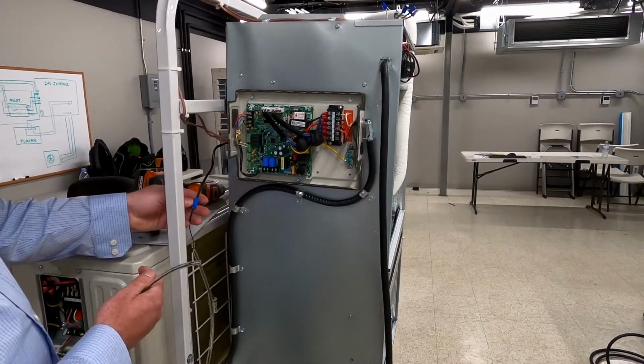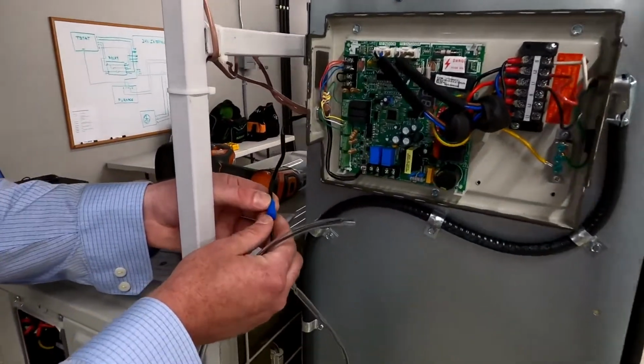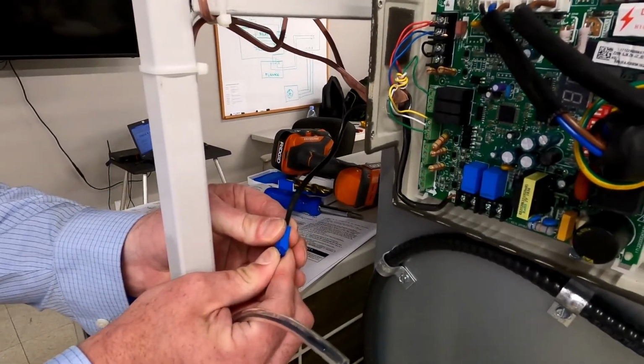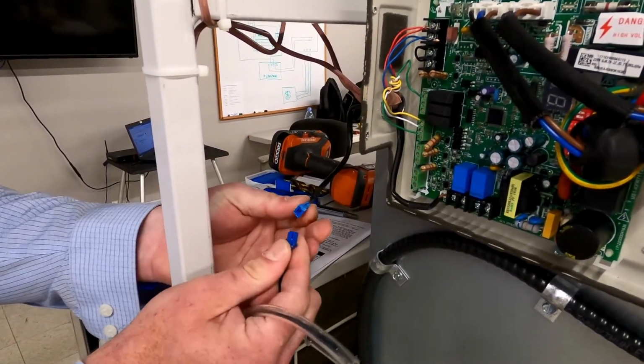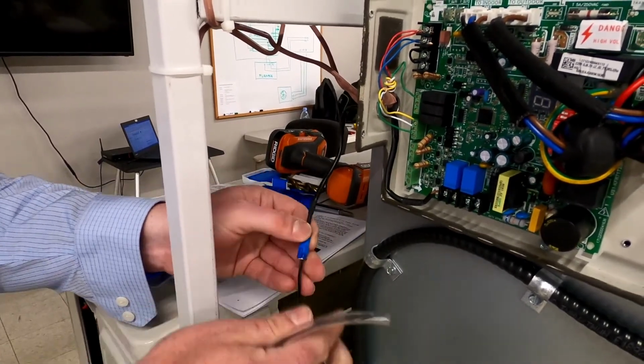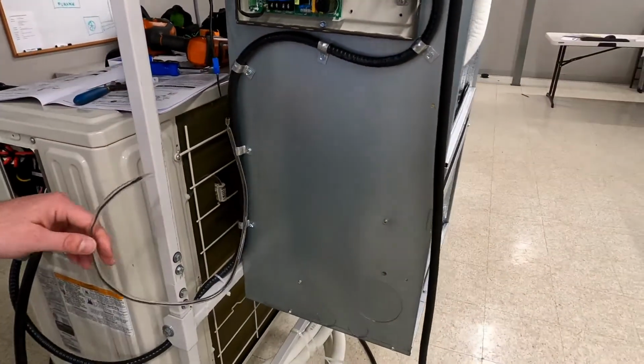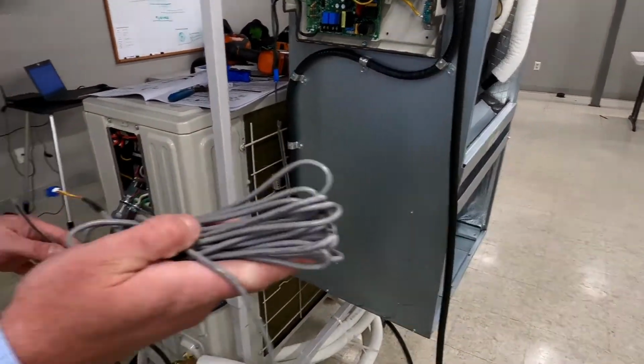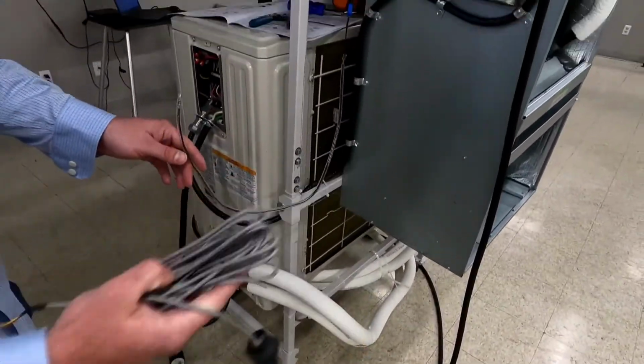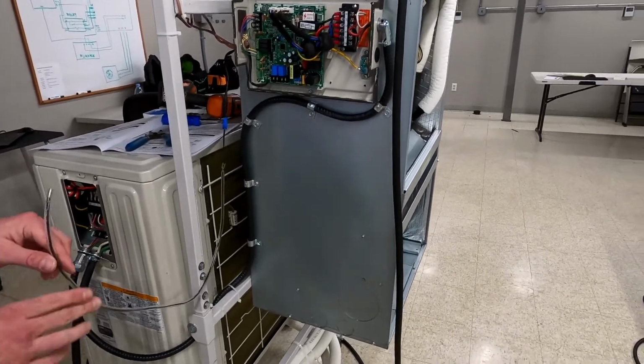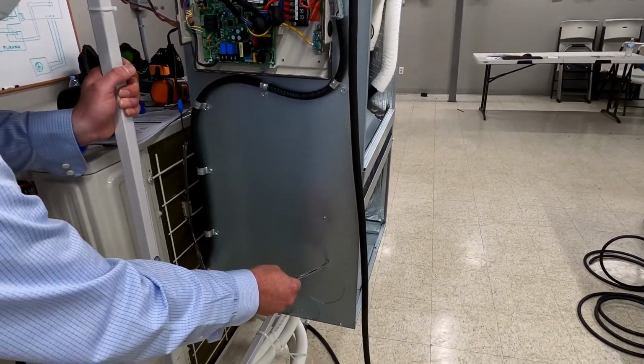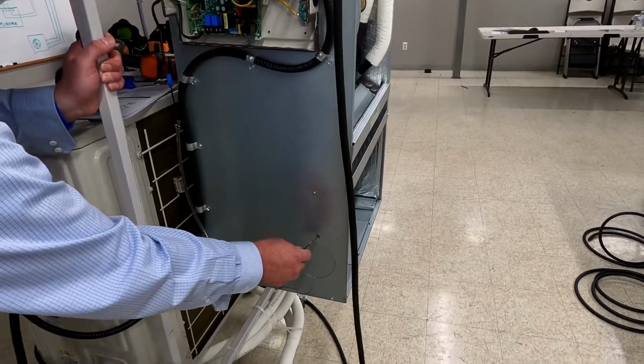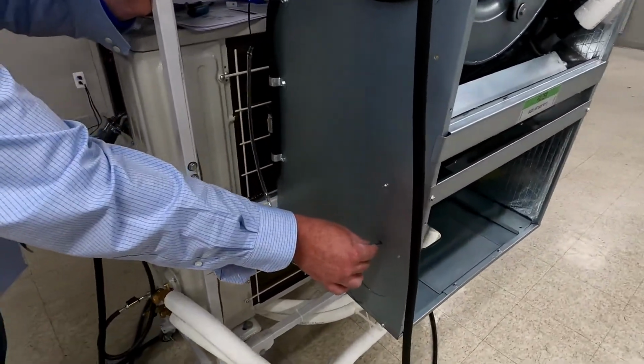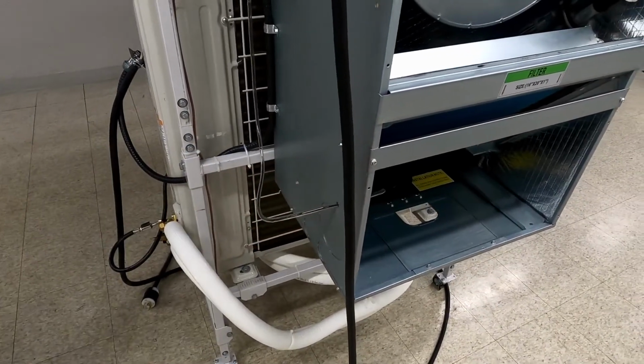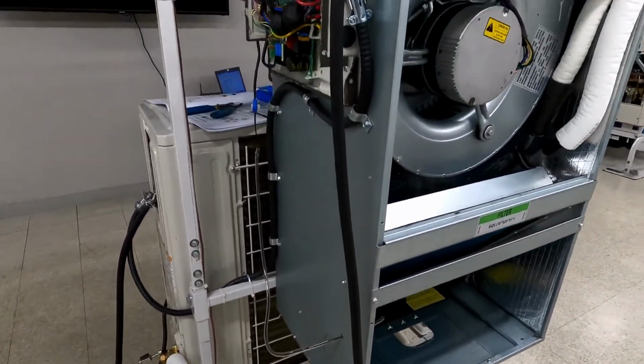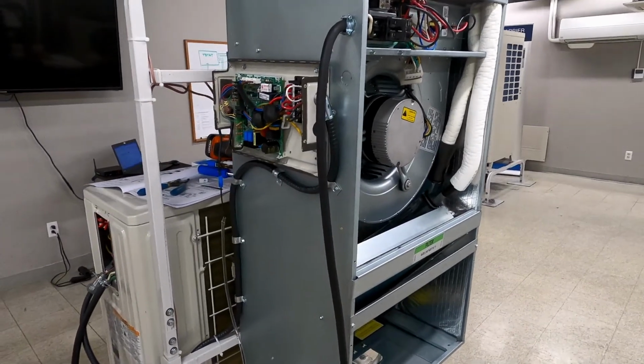The last step required in this installation when hooking up the 24 volt interface kit is to install the return air thermistor. So the interface kit has a pigtail that comes off it, and you plug in your thermistor to that pigtail. If your interface kit is further away, there's also an extension wire that you can use to extend the length. The reason we need this return air thermistor in this setup is so that the interface kit knows what the space temperature is by using the return air temperature to sense that. This is necessary to maintain variable speed operation with the outdoor unit.